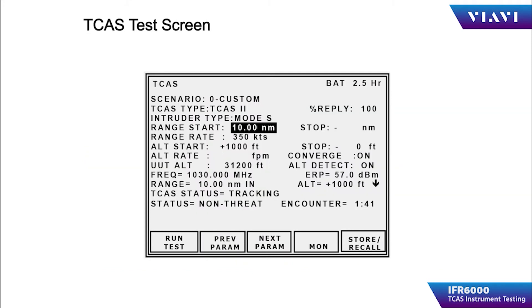Pressing the TCAS instrument key initiates the TCAS test instrument. The IFR 6000 can be used for over-the-air testing of the aircraft systems. The TCAS test operation screen is where the operator can configure the physical parameters of the simulated target such as start distance, altitude, altitude rate, and velocity. It also provides the basic measurements of the TCAS being tested such as frequency, power level, and whether the target is being tracked.